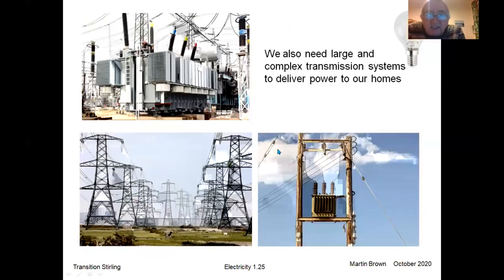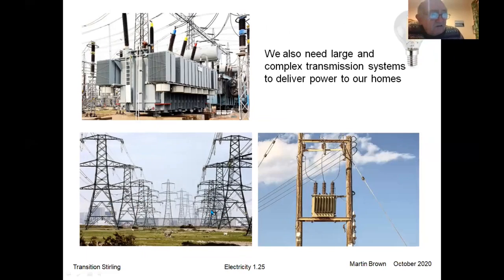Okay, we've talked about the generating side of it. I won't go into the detail, but you need a very complex transmission system to get the power around. And whether we like it or not, pylons are the most cost-effective way to shift power around the country. If you start burying cables, you have to cool them, you have to do all sorts of things. So pylons are what we're stuck with. These little things and these big things are the transformers that I talked about. And without going into too much detail, we always transform to as high a voltage as we can work at, because that minimizes our transmission losses. If you transmit at low voltage, you get a lot of losses.